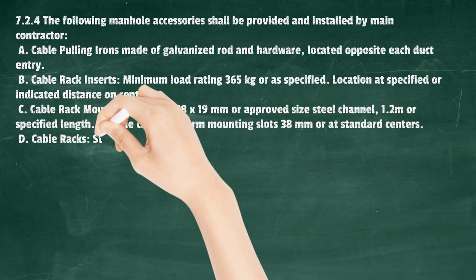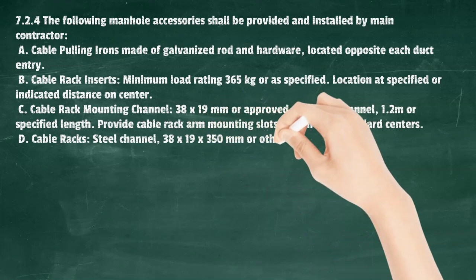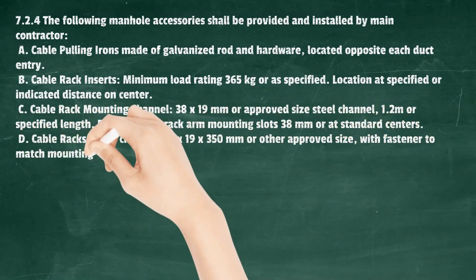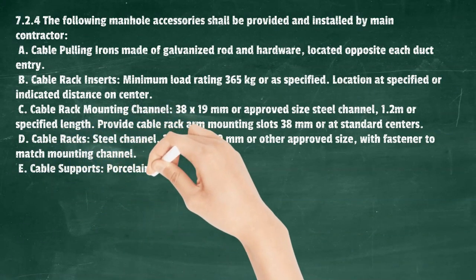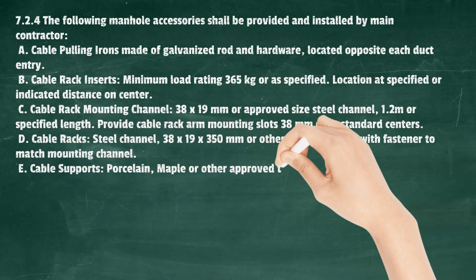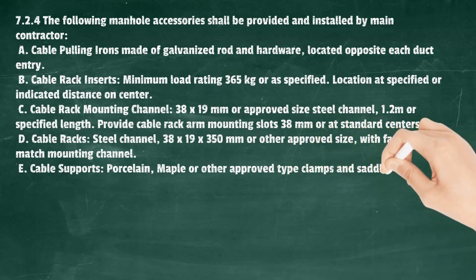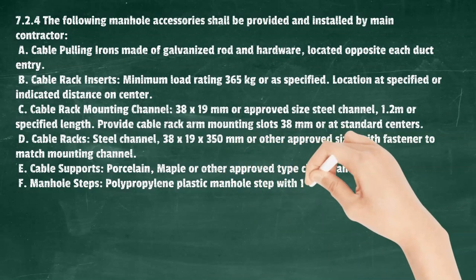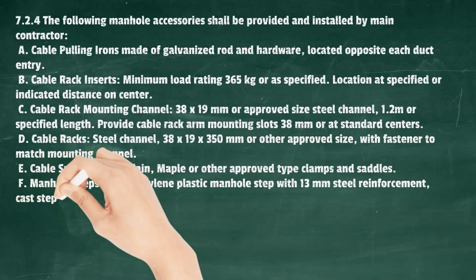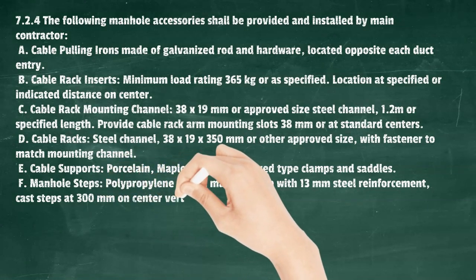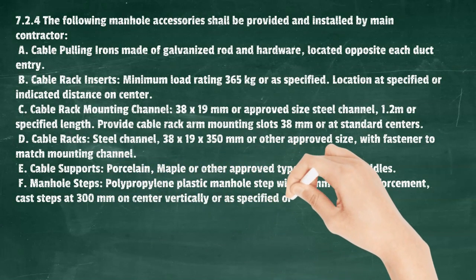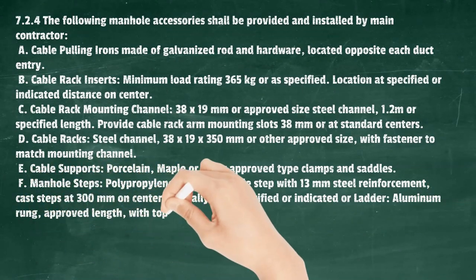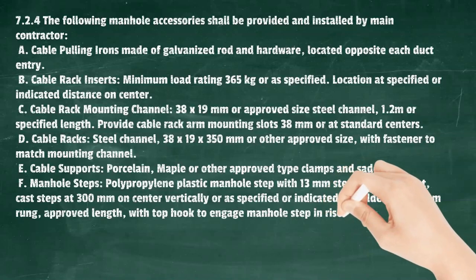D) Cable racks, steel channel 38 x 19 x 350 mm or other approved size, with fastener to match mounting channel. E) Cable supports: porcelain, maple, or other approved type clamps and saddles. F) Manhole steps: polypropylene plastic manhole step with 13 mm steel reinforcement, cast steps at 300 mm on center vertically or as specified; or ladder, aluminum rung, approved length, with top hook to engage manhole step in riser casting.